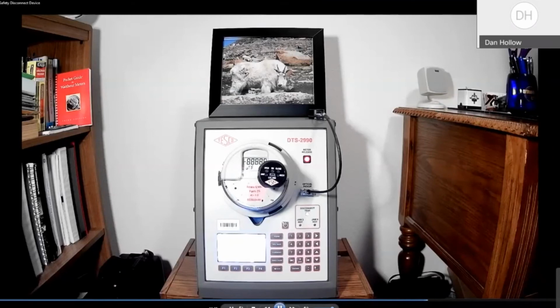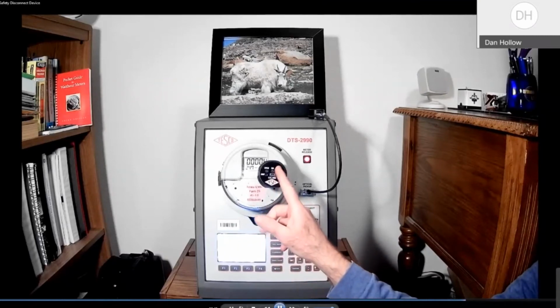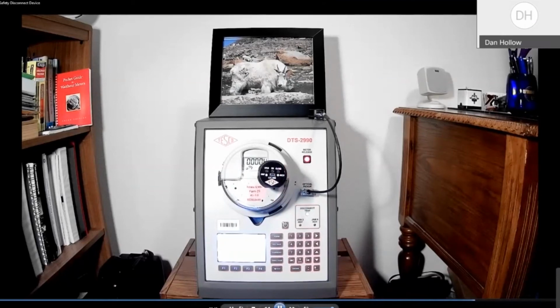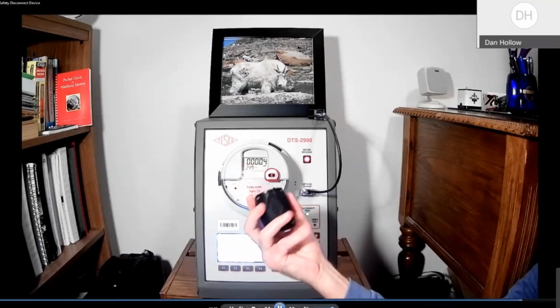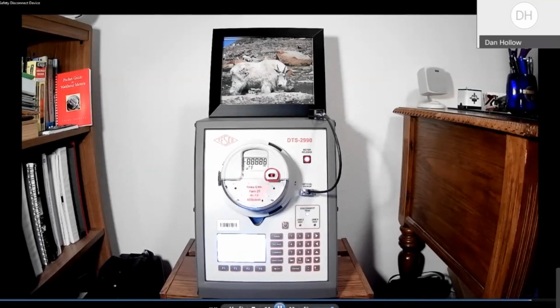So all you have to do, since the device is still awake, is go ahead and hit close. You'll notice the 2 LEDs on the test board are off, indicating the open state of the service disconnect switch in the meter. So now we'll just hit close, and it will close the switch in the meter and turn the customer's power on. There's a little delay on this particular meter, a little different than other meters. Some meters have a delay, others do not. I can actually remove this device at this point and just wait a bit, and then the contacts close and customer power is back on.